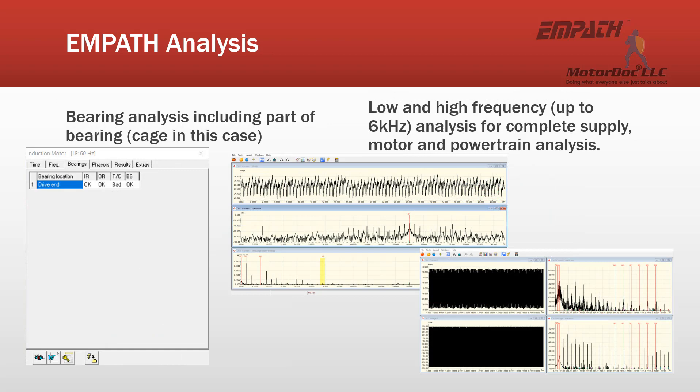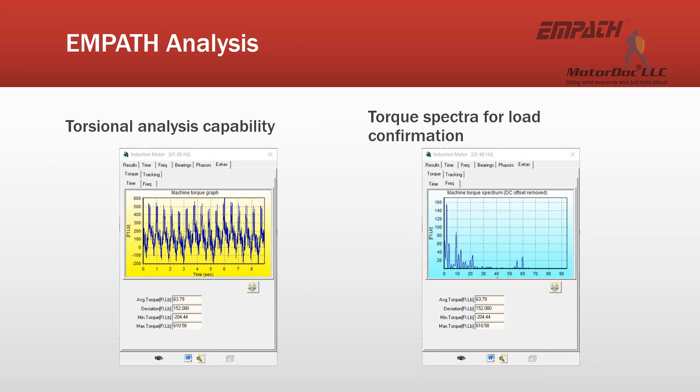It will also look at bearing analysis, including parts of the bearing — in this case, it was identifying a bad cage. And then low and high frequency analysis up to 6 kHz for complete supply, motor, and powertrain analysis, basically from incoming power to driven equipment. It will also perform a torsional analysis, including time waveform and full spectra for the torque.